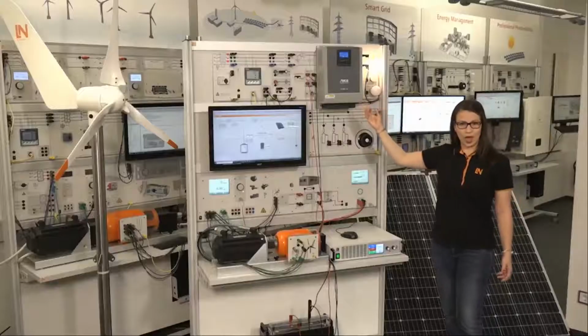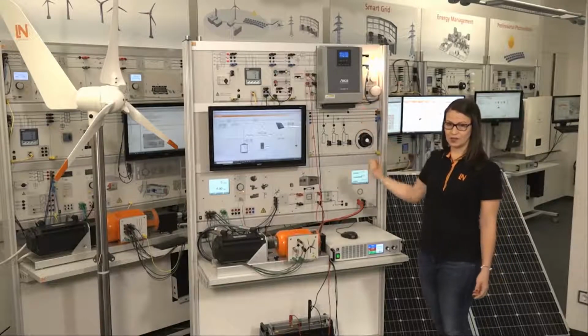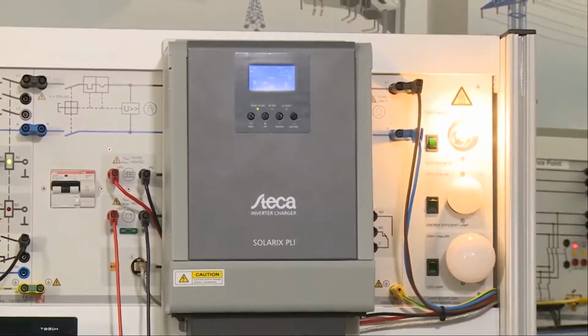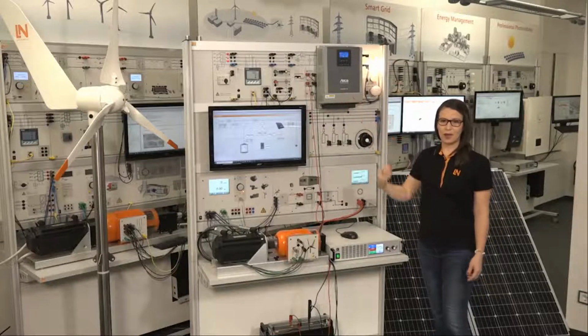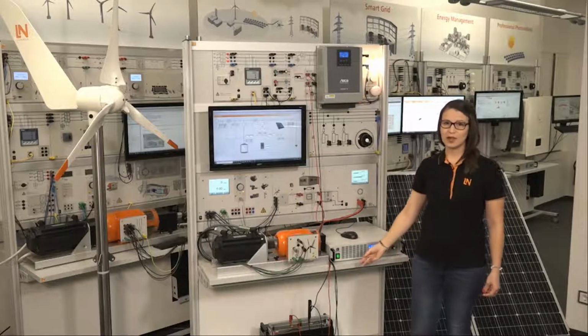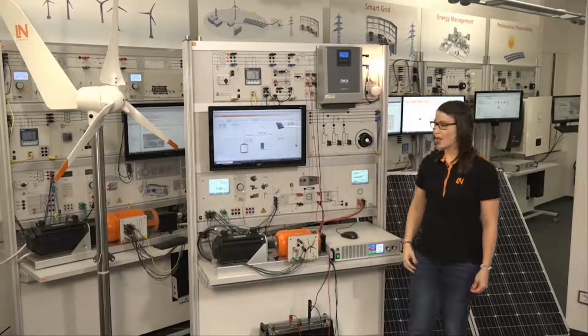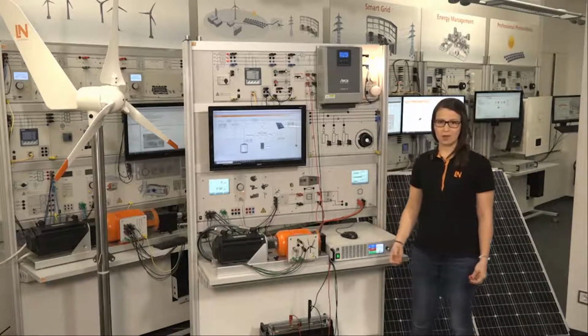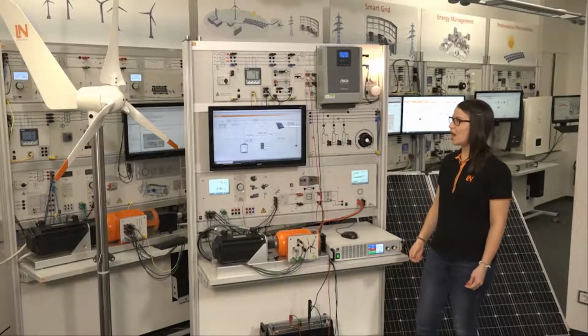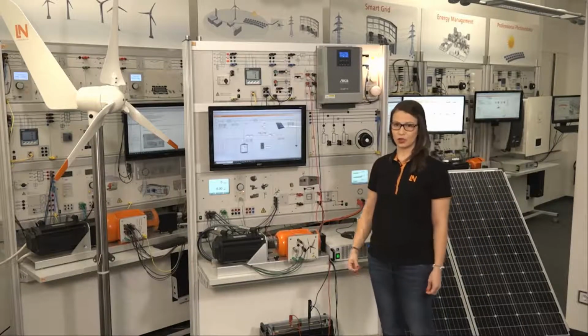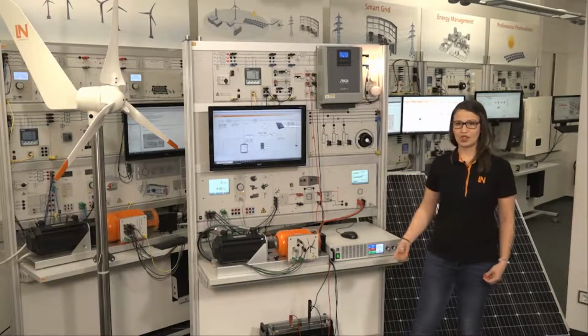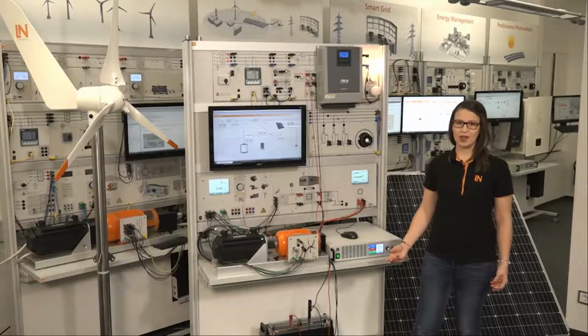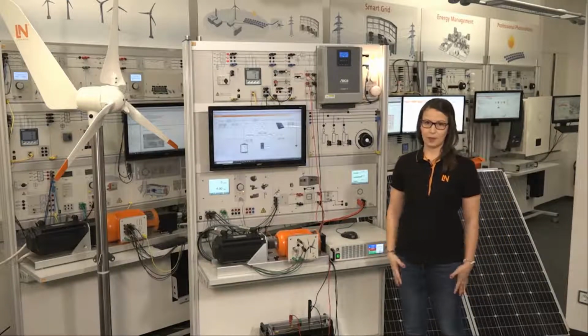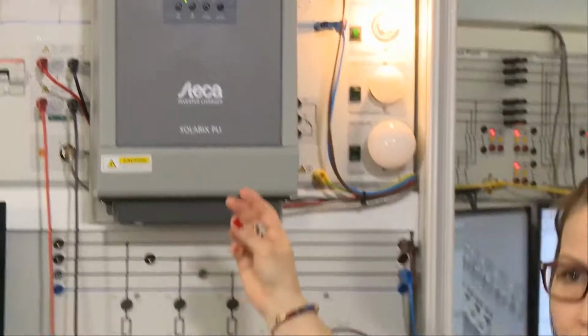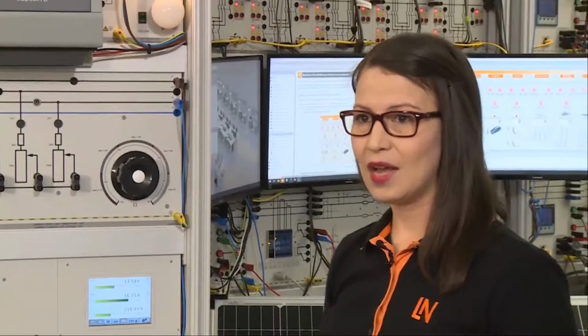In the middle, we have the most important element of the system, the battery-powered inverter. This device, apart from operating as an inverter with battery management, also has a solar charge controller with MPPT, and an AC charge controller, so the battery can be recharged when the capacity level is too low, for example at night. This device also has a measurement module which collects data and sends it to the SCADA.